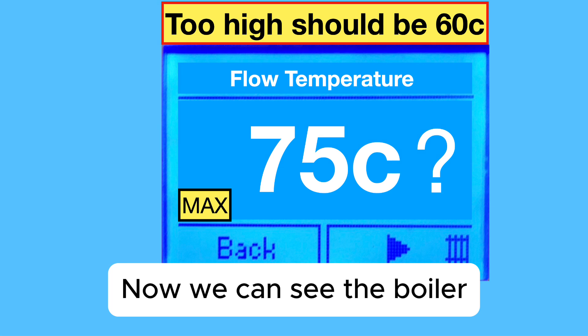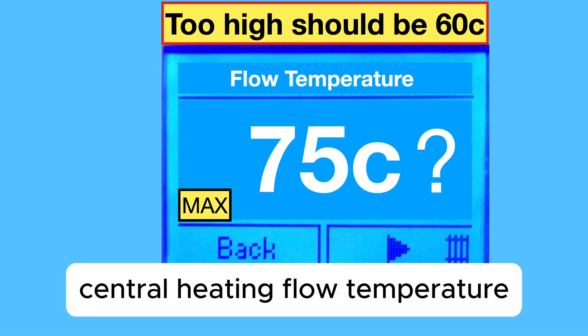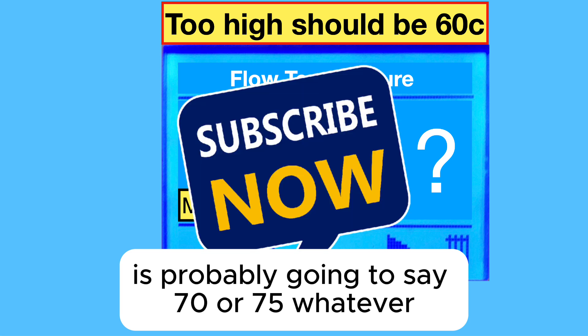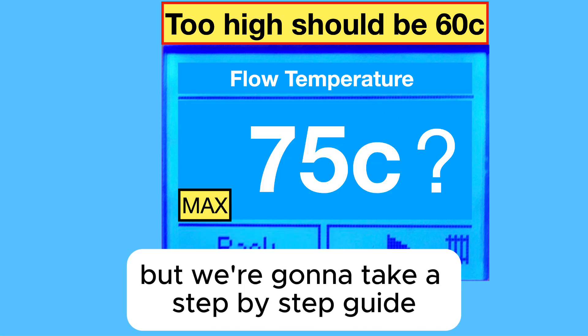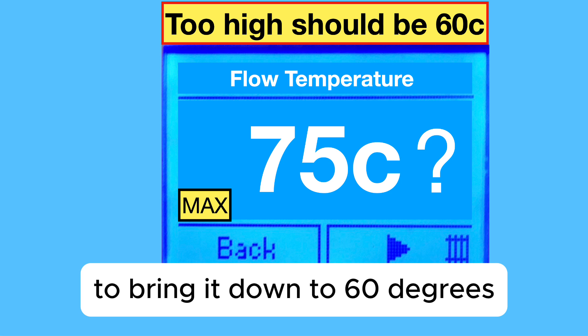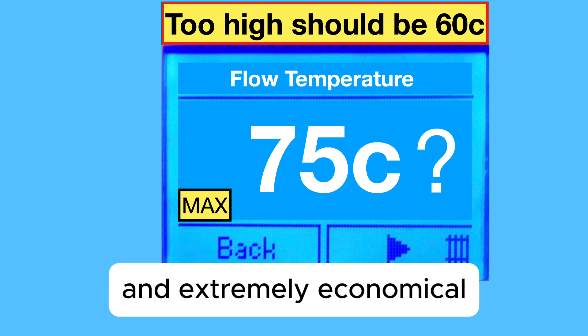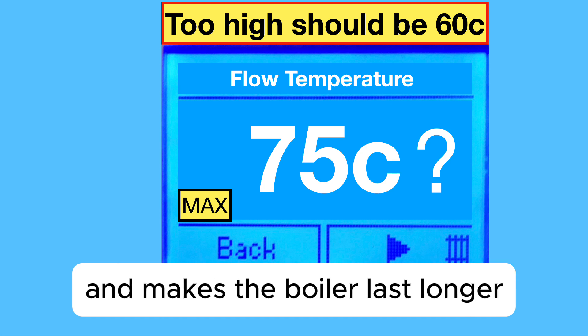Now we can see the boiler central heating flow temperature. It's probably going to say 70 or 75. But we're going to take a step-by-step guide to bring it down to 60 degrees, which makes it lean, green and extremely economical and makes the boiler last longer.